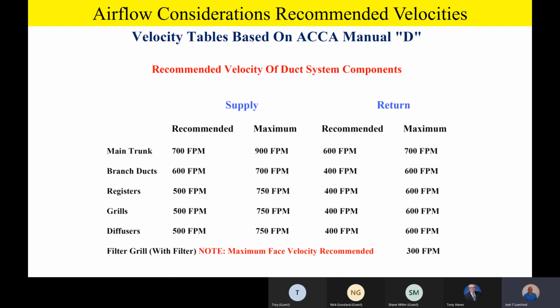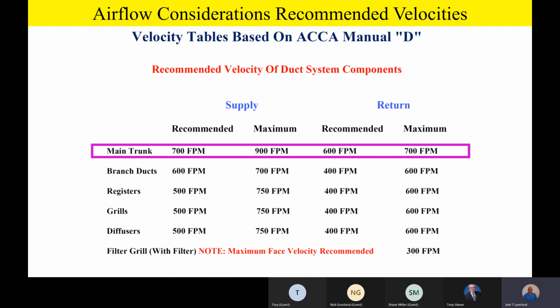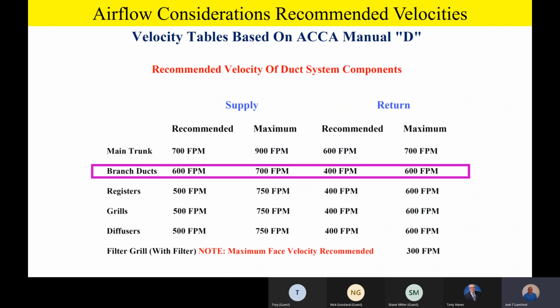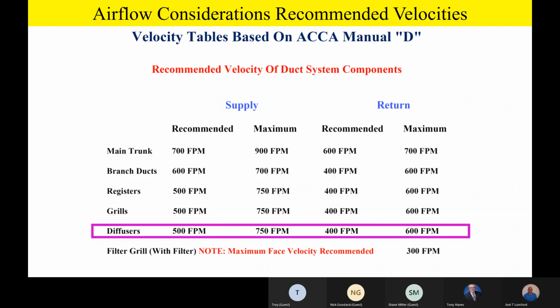Some other considerations, team, is please remember velocity tables in Manual D. If you open up Manual D, you'll see there will be some velocity considerations for duct systems, supply and return duct. Please look at those because there'll be main trunk and branch duct considerations as far as recommended velocities in all of our duct components.